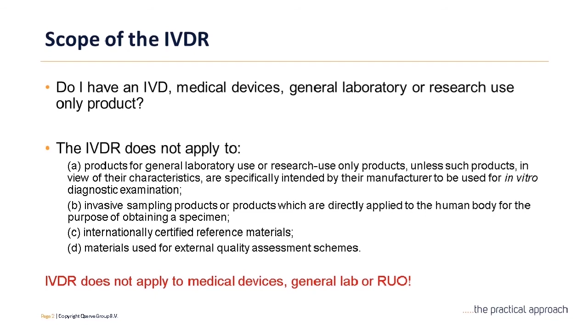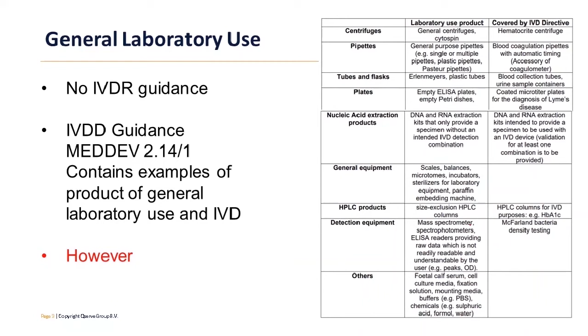So at the moment, we don't have any guidance for the IVDR. However, there is guidance for the IVD directive. So you have to bear in mind this is not written for the IVDR, but it's still a good source of reference. So this MedDev 2.14/1 is about general laboratory use. And it tells us things like pipettes and centrifuges are just general laboratory use unless you've made some special modification for them to become an IVD. It also gives you other examples, for example, reagents for nucleic acid extraction. If they could be used for any application, for research applications, and there's no special intended purpose or change to the product to make it an IVD, they just remain as general laboratory use. Also think about things like media that could be used for environmental monitoring, for example. They're general laboratory use, they're not IVDs.